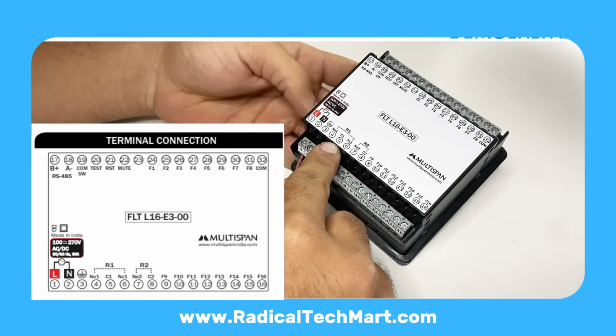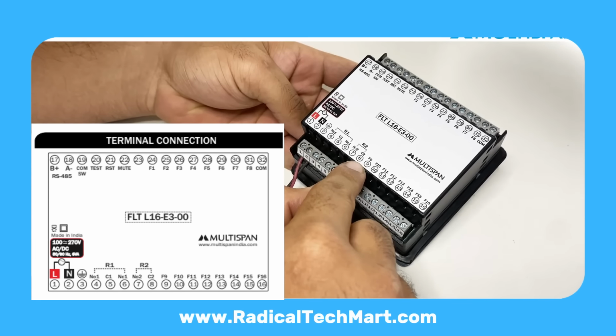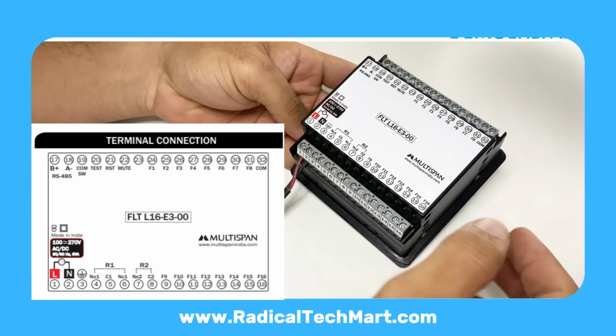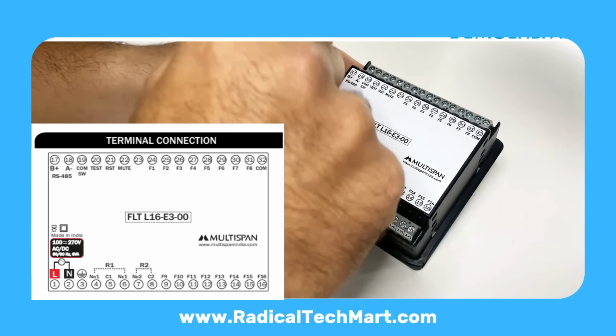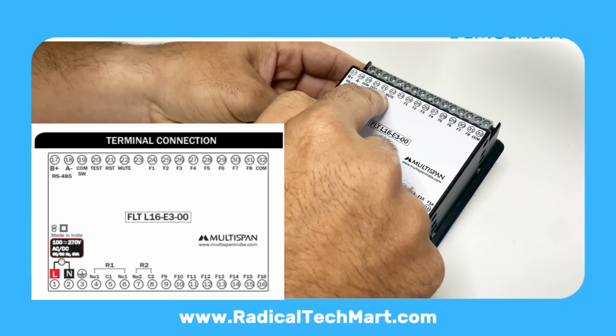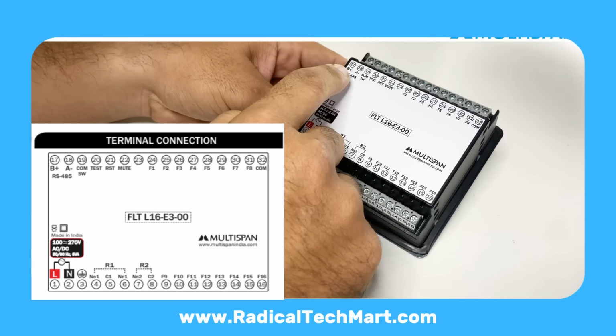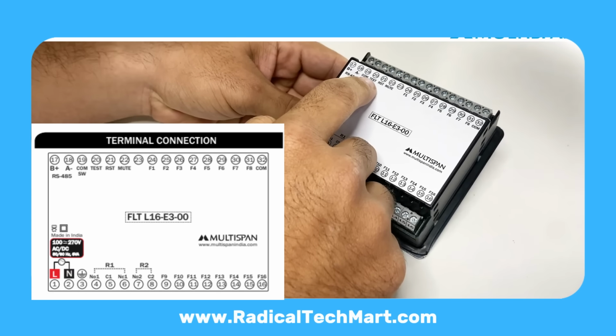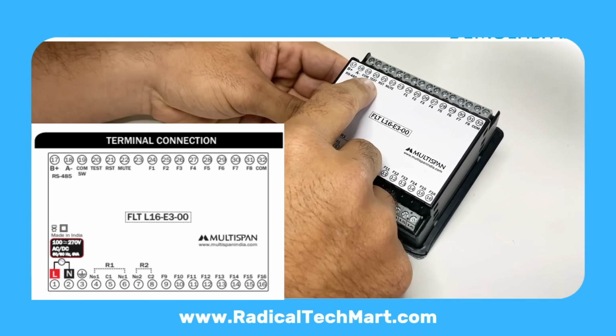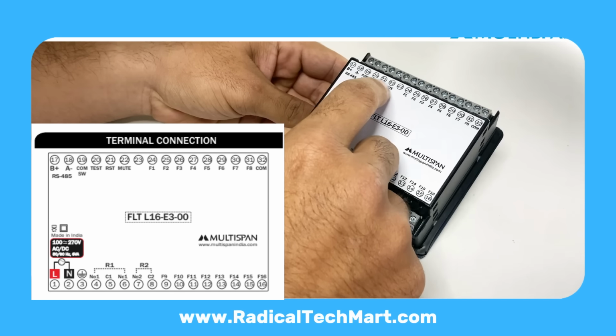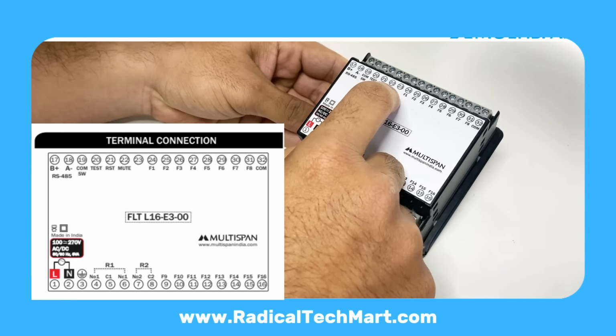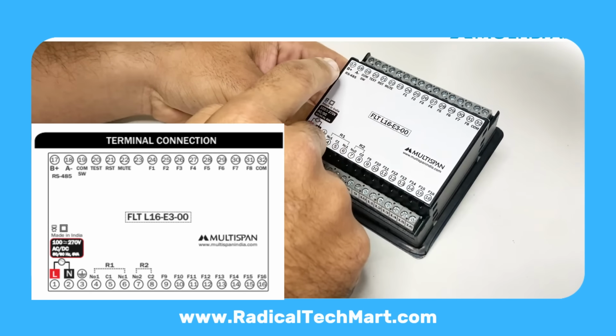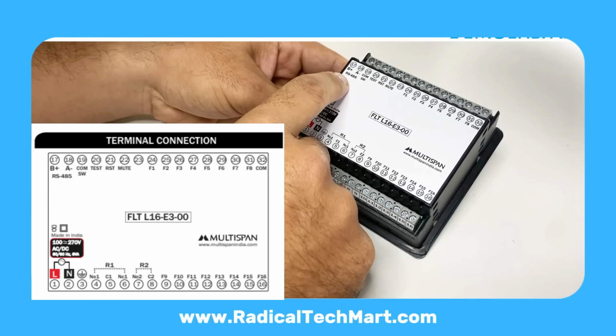So if any fault occurs in the field, the alarm relay can alert you, and the trip relay can isolate that section or stop equipment. On the front, you also get individual push buttons for test, reset, and mute. With these, you can simulate a fault and test the system, reset acknowledged faults, and mute the audible alarm right from the panel in the field.